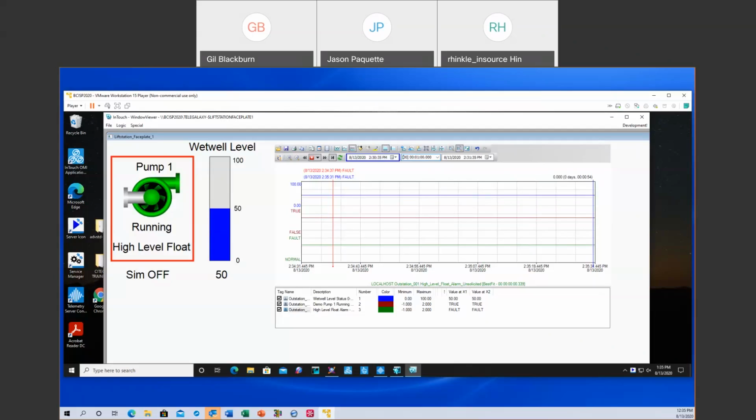Yeah. Next question. Could the DNP3 master read the digital outputs or just the digital inputs? For example, if the output in the PLC changes, does the master DNP3 read the output status? Now, it depends on the RTU. I will say this. For the binary outputs, if the RTU supports doing timestamped events on the digital outputs, the answer is absolutely yes. If it doesn't, you'll need to map them back into digital inputs. But yes, we can absolutely read the status of those points. That's where it kind of gets a hybrid answer.